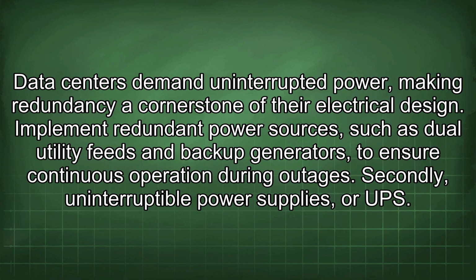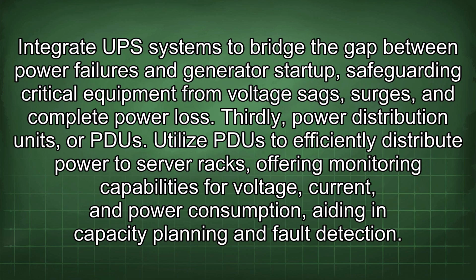Implement redundant power sources, such as dual utility feeds and backup generators, to ensure continuous operation during outages. Secondly, uninterruptible power supplies, or UPS. Integrate UPS systems to bridge the gap between power failures and generator startup, safeguarding critical equipment from voltage sags, surges, and complete power loss. Thirdly, power distribution units, or PDUs.